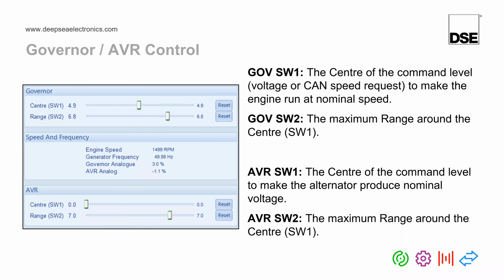Yeah, I'd just like to add a couple of extra points to that as well, because it is a very good question, and it is something that occasionally we do get asked at DeepSea. Now, what David said is completely correct. You can adjust the switch 1 or switch 2 values to compensate for voltage drop across a cable. However, in all honesty, the amount of voltage drop you would get should be very, very small. The reason for that is most voltage signals carry very small amounts of current, and it's current down a cable that creates voltage drop.